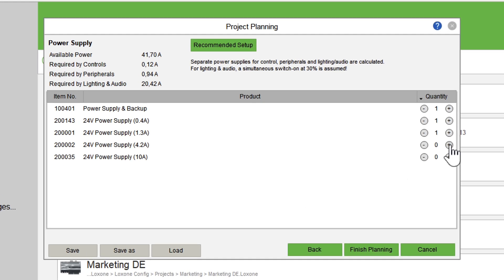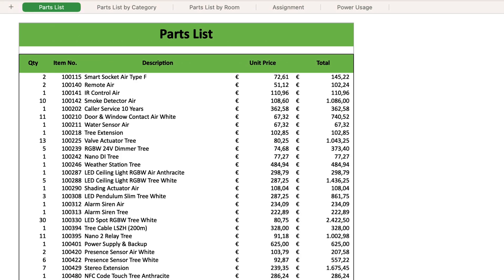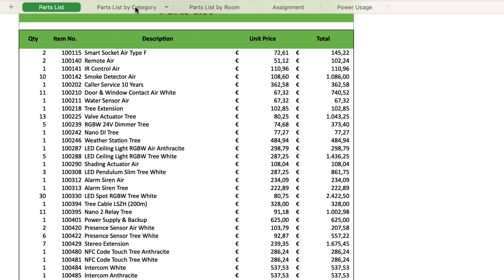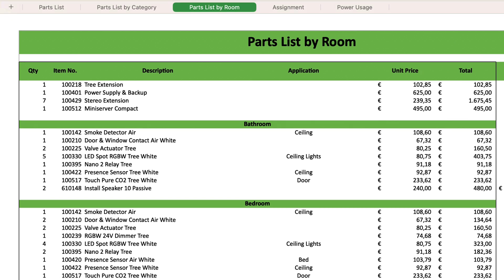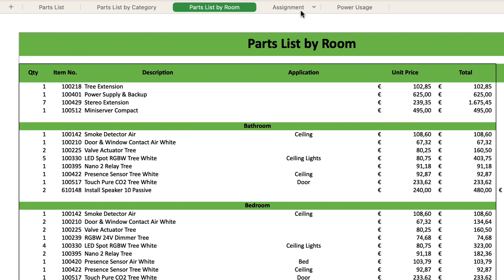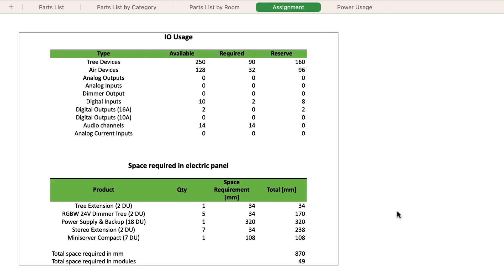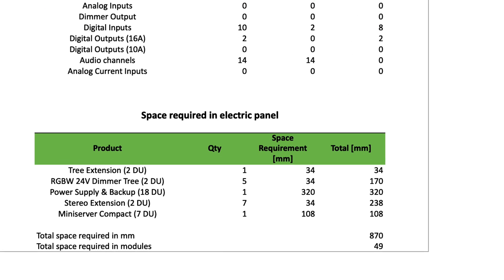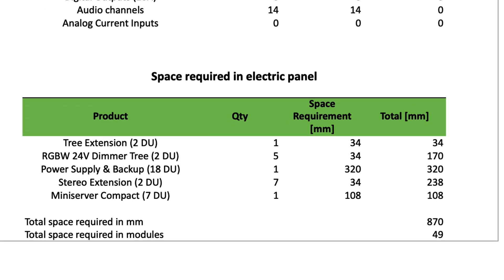The project planning tool also calculates the required power of the power supplies. At the end we get a complete list of all the components that can be used to create an offer, clearly sorted by room or category, as well as an overview of the assignment of the inputs and outputs. It is also important to know how much space is required. All components from the control cabinet are listed here with size, so we know exactly how big the control cabinet has to be.